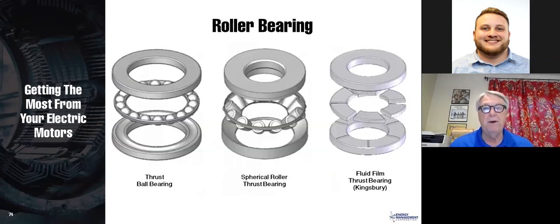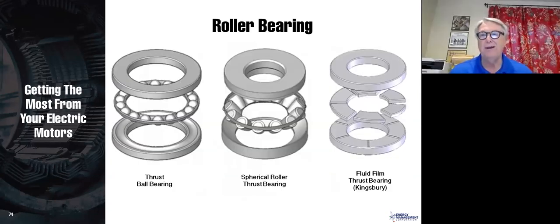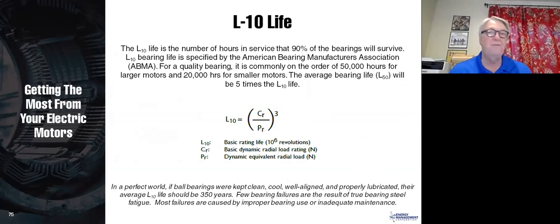Here's a thrust ball bearing, a spherical roller bearing, and a fluid film bearing. The fluid film bearing is sliding. The whole thing is sliding, and typically these are in oil baths. L10 life. The L10 life is the number of hours in service that 90% of the bearings will survive. And so we typically like to see an L10 life of about 50,000 hours for larger motors and 20,000 hours for your smaller motors.